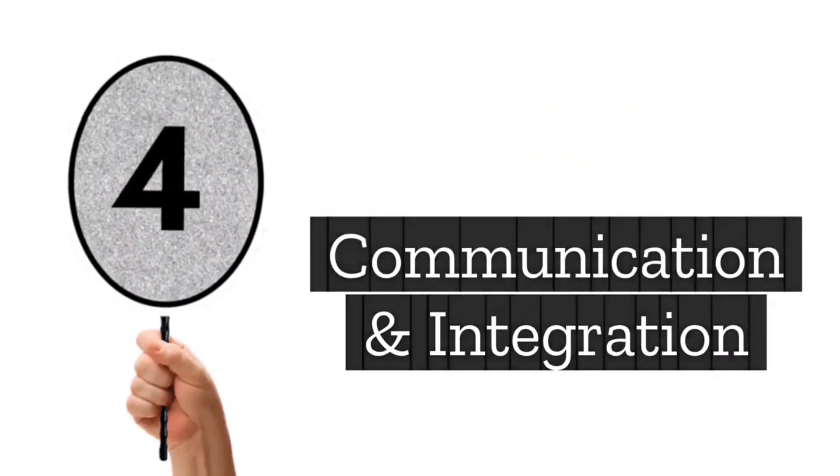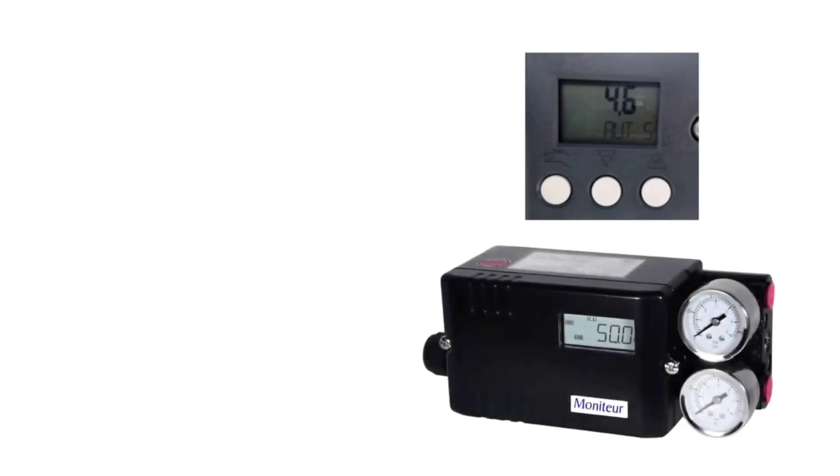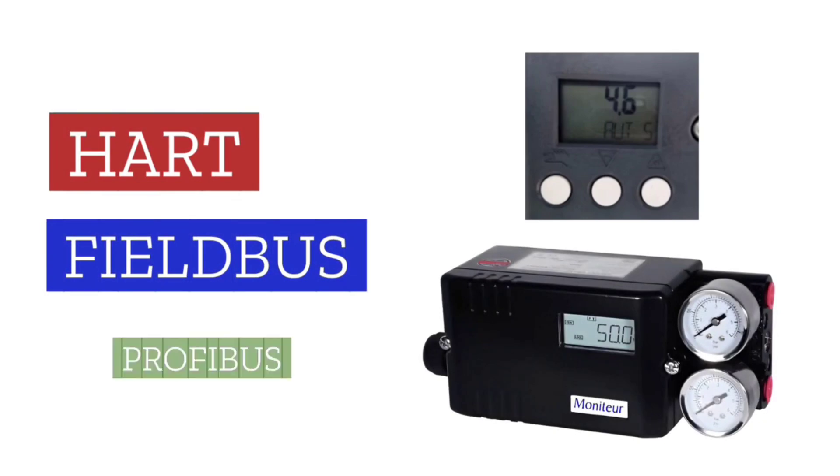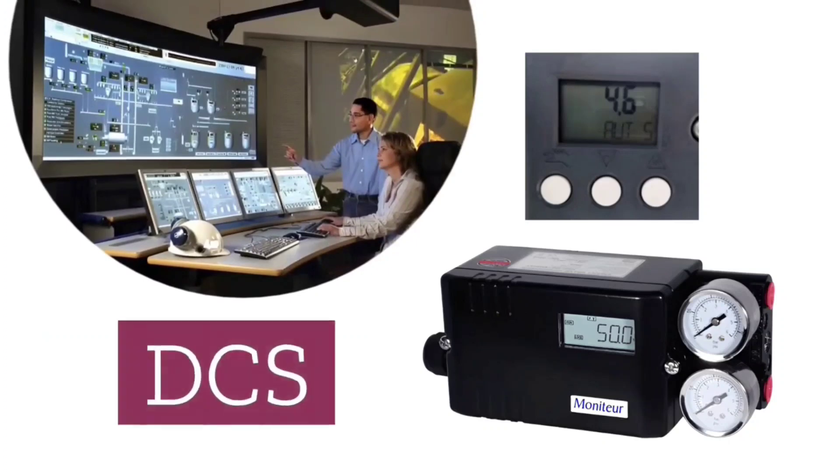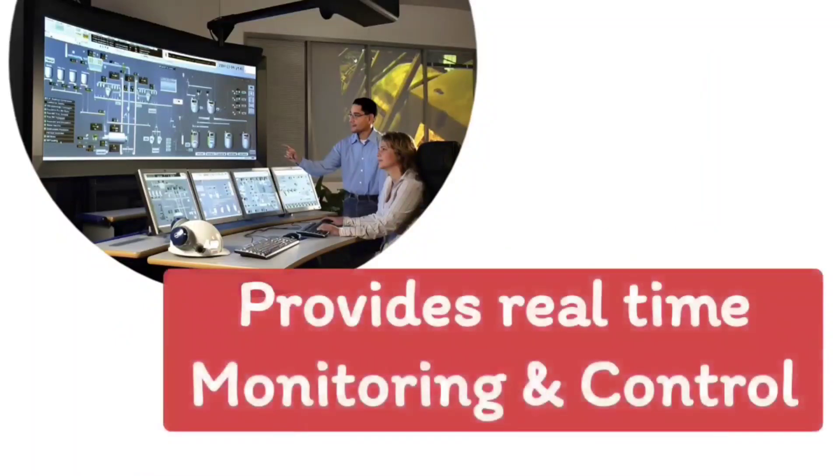Next is communication and integration. Smart valve positioners are equipped with a communication protocol such as HART, Fieldbus, or Profibus. It can be integrated with distributed control systems, means DCS, and automation systems. And this provides control valves real-time monitoring and control.